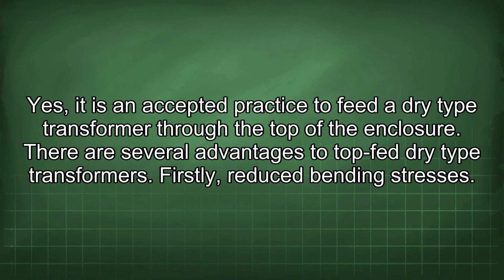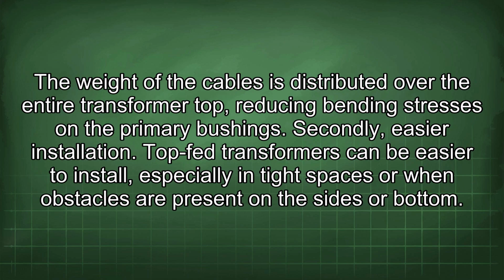Yes, it is an accepted practice to feed a dry-type transformer through the top of the enclosure. There are several advantages to top-fed dry-type transformers. Firstly, reduced bending stresses. The weight of the cables is distributed over the entire transformer top, reducing bending stresses on the primary bushings. Secondly, easier installation.